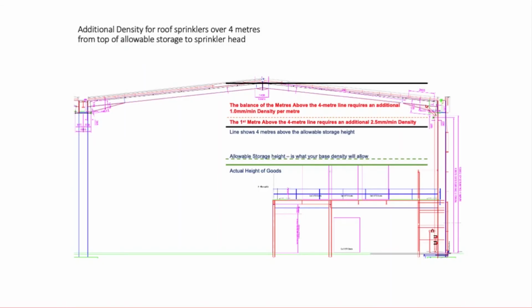When roof sprinklers are more than 4 metres from the top of the allowable storage, you need to add density. For instance, if that's the height of your stored goods, once you work out your base density, you might be able to store up to what we call the allowable storage height.